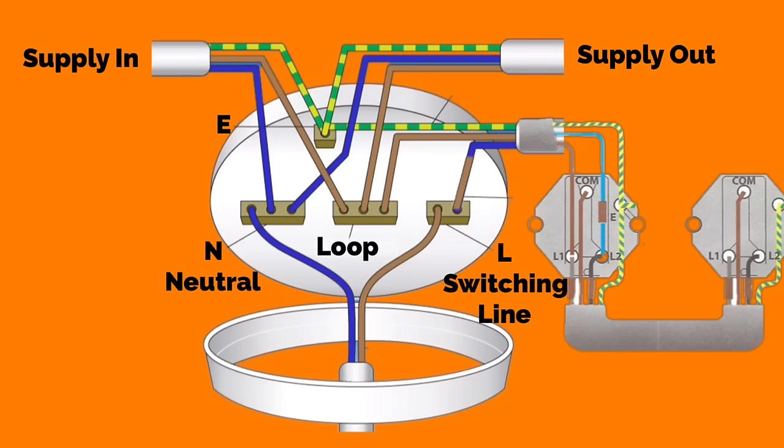When working in ceiling roses and pendants in domestic dwellings, you may also be faced with cable colours pre-2004. Pre-2004, the line conductor was red, the neutral conductor was black and as it still is, the circuit protective conductor was identified with green and yellow sleeving.